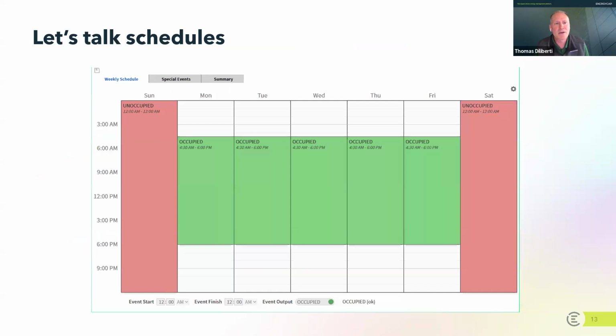Okay, so let's make the jump now to taking a look at a number of different screenshots. Let's start by talking schedules, because this is where I always want to encourage you to start. What you see on your screen here is an example of what's called a weekly schedule. The green bars represent how the building is being scheduled Monday through Friday. You can see that very clearly shows up. The building on Sunday and Saturday is in an unoccupied mode. Many times, if it's not occupied by default, it'll go into the unoccupied mode. So if you notice in each of the days, Monday through Friday, where there's white and not the red of the unoccupied, it's also in the unoccupied mode. Depending upon the system, they will allow you to schedule occupied or unoccupied or both. But this is just what a typical system would look like, and this is where I really want to encourage you to start.